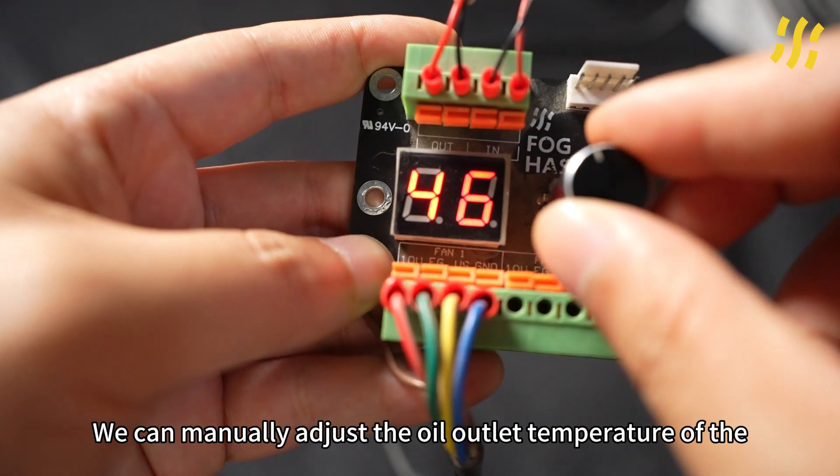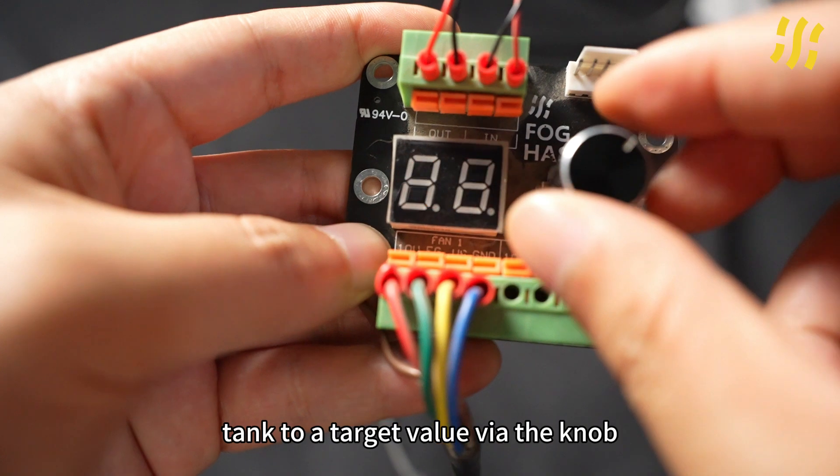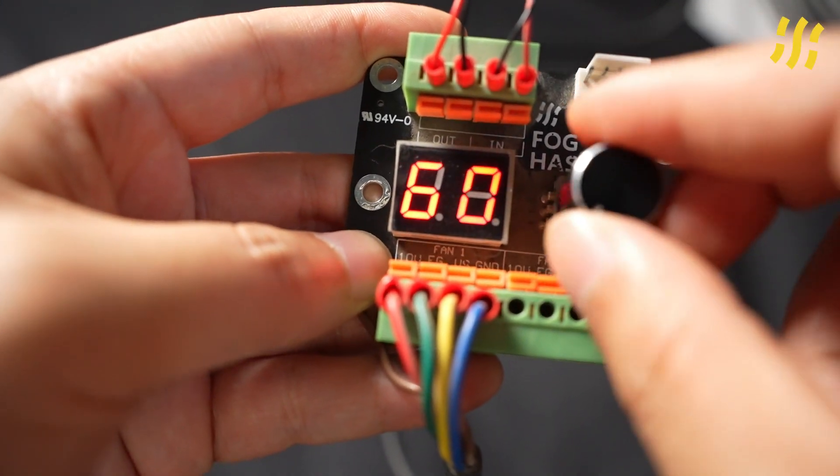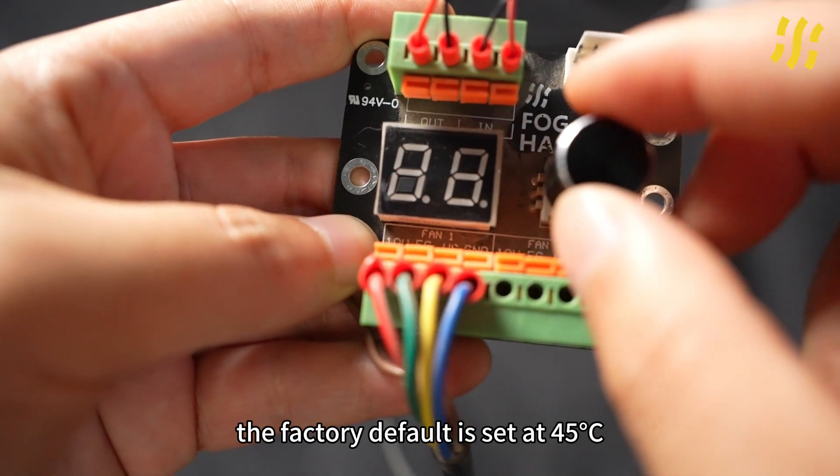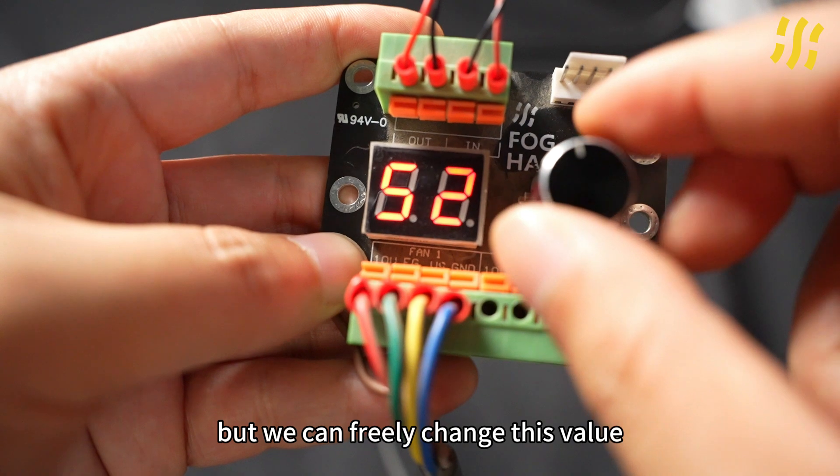We can manually adjust the oil outlet temperature of the tank to a target value via the knob. Typically, the factory default is set at 45 degrees Celsius, but we can freely change this value.